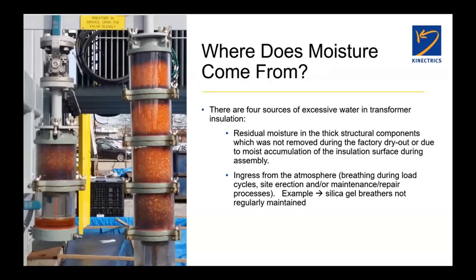Another source of moisture getting into the transformer, well, you can blame some of it on our friend in the picture on the left there, which is a silica gel breather. A silica gel breather is used on a transformer because as the transformer operates, high load, low load, high temperature, low temperature, the oil expands and contracts. And as the oil expands and contracts, we need a way for the gas space somewhere in the transformer, whether it's in the tank, in a sealed unit, or in the conservator tank, in those designs, we need to allow air to come in and out. And we want that air to be dry. And so we have the silica gel breather.